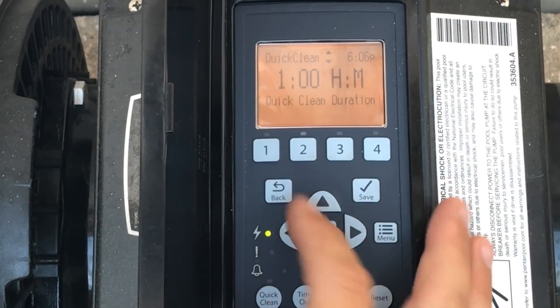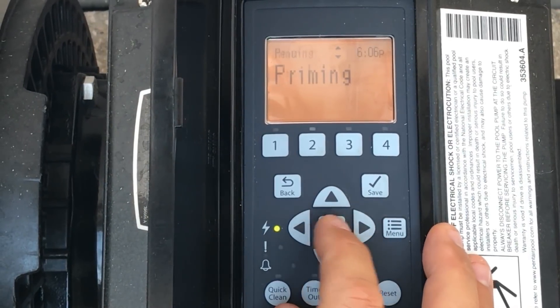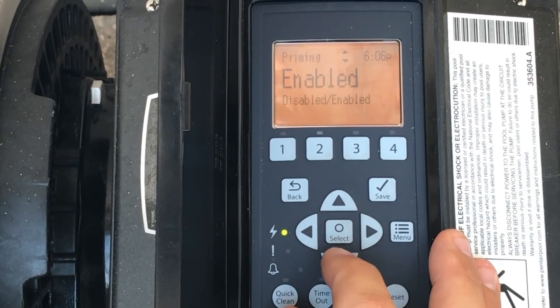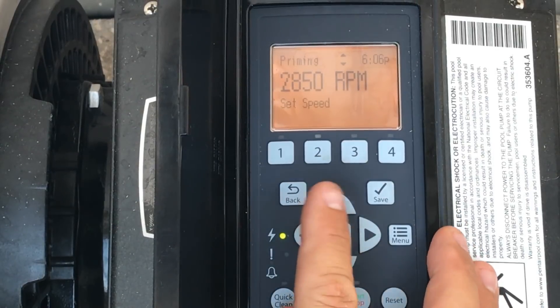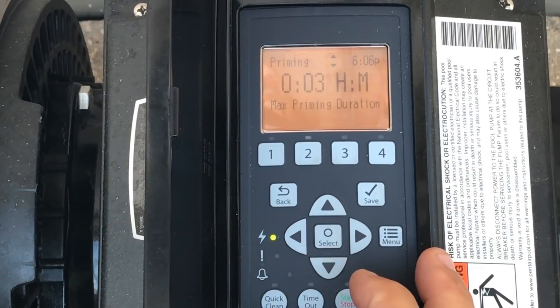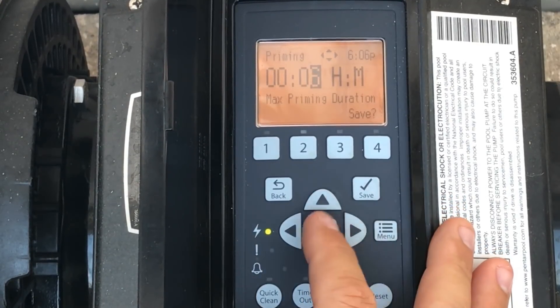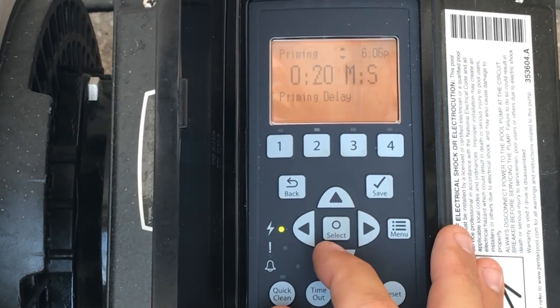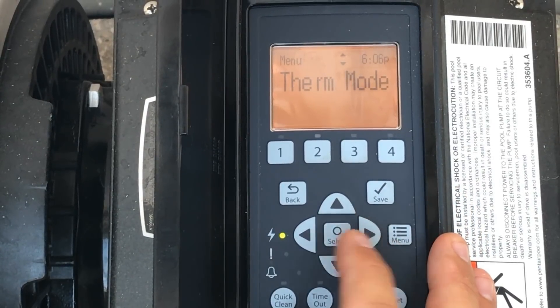Under priming, if you want to change how this pump primes — or disable it entirely — you'd change it here with enable and disable. The priming speed can't exceed your max of 2850 RPMs. We're going to change the priming duration to six minutes, because by definition a self-priming pump is one that primes itself within six minutes.